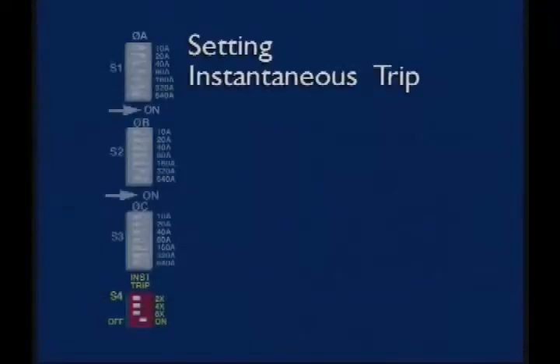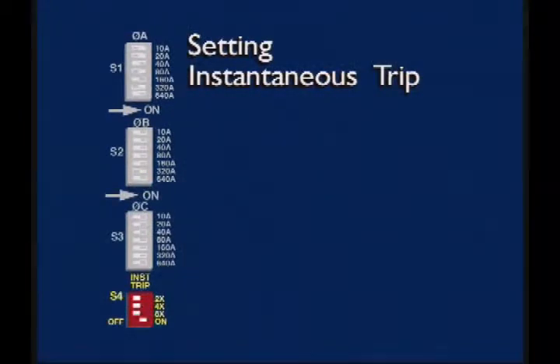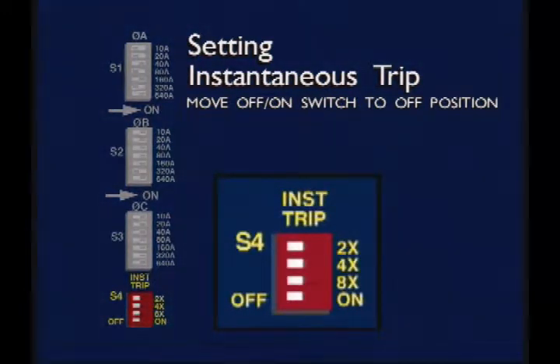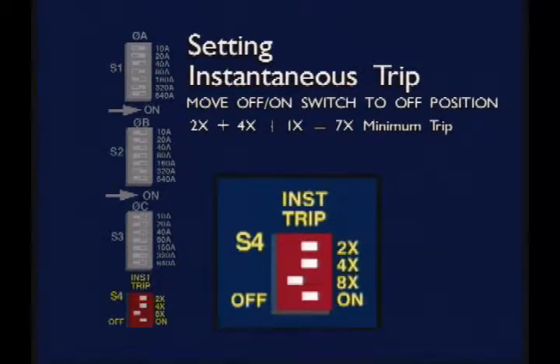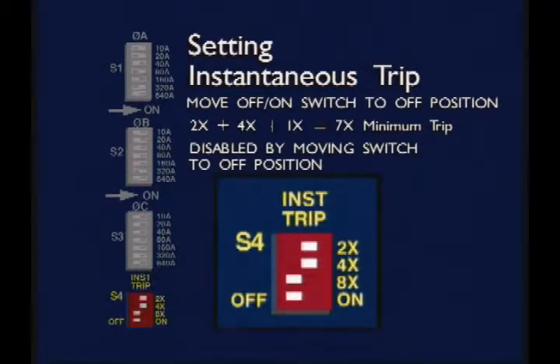The instantaneous trip multiplier may be programmed from 1 to a maximum of 15 times in odd number increments. Each phase may be set at a different minimum trip setting, but the instantaneous trip multiplier is common for all phases. Refer to the control settings decal. Before setting instantaneous trip on an energized unit, set the off-on switch to off. The off-on switch activates instantaneous trip and provides a 1 times multiplier. For example, to set the instantaneous trip at 7 times minimum trip, set the 2 times and 4 times switches to on. Lastly, set the off-on switch to on for a total of 7 times minimum trip. The instantaneous trip feature is disabled by moving the off-on switch to off.